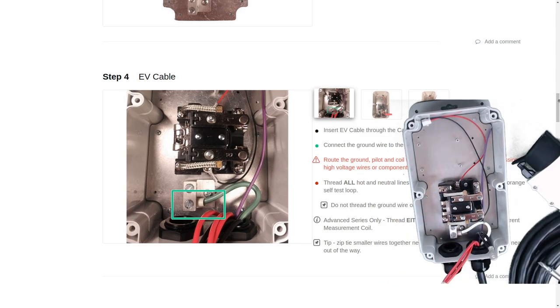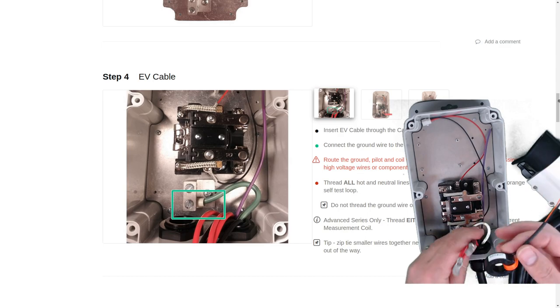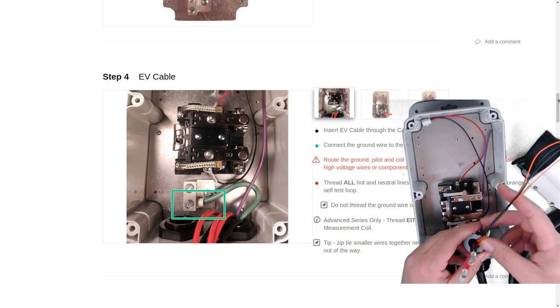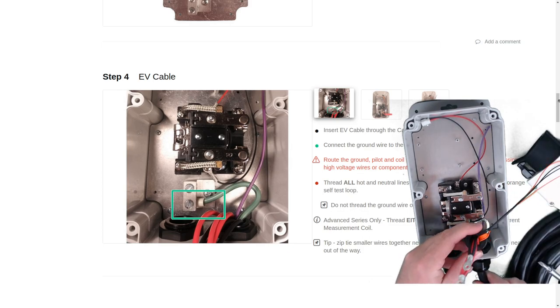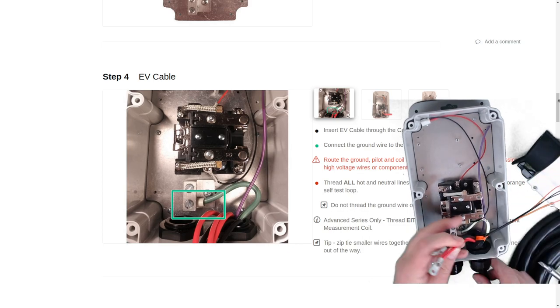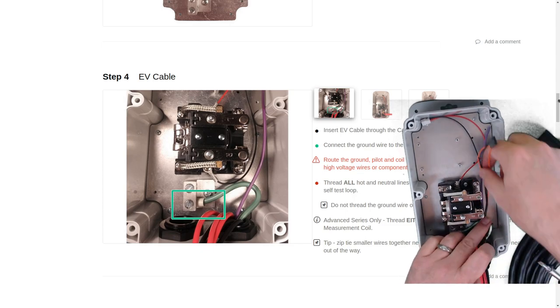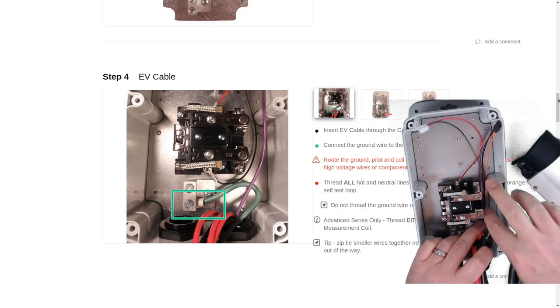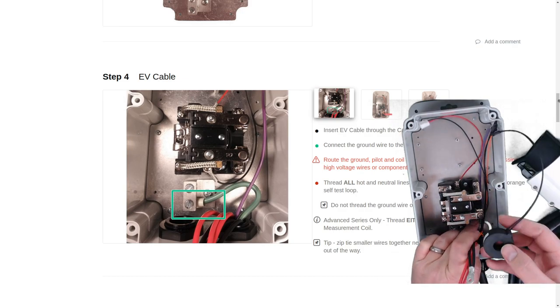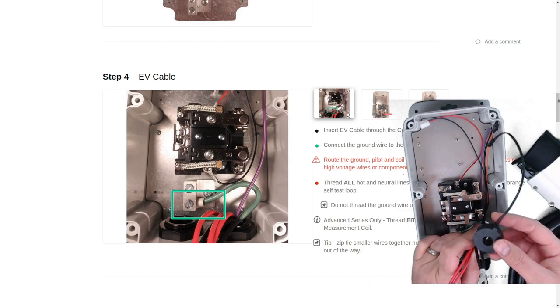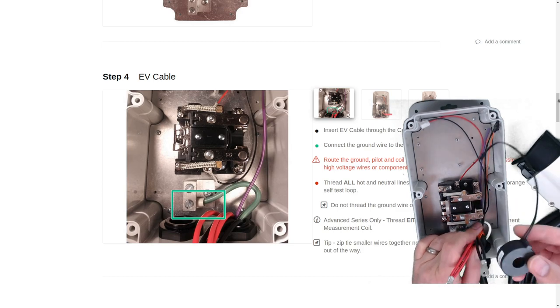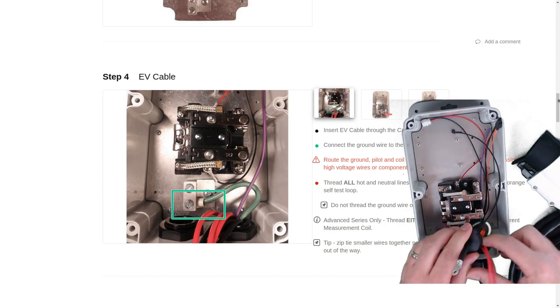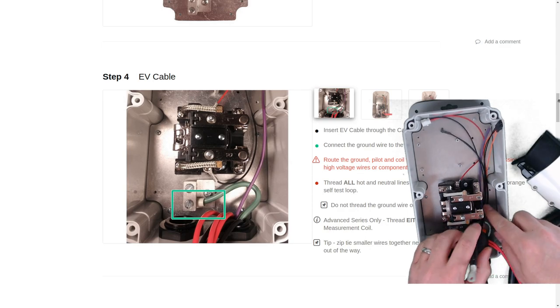Next, we'll bring in our coils. And the first one that will go on is the GFCI safety coil. We're going to put that over both the black and the red wires. And then we're going to lay this wire down low in the enclosure with the other wires. Next, we'll put on the current measurement coil. This is going to go on just one wire. And we'll put that on the black wire and move the red wire over to the side.